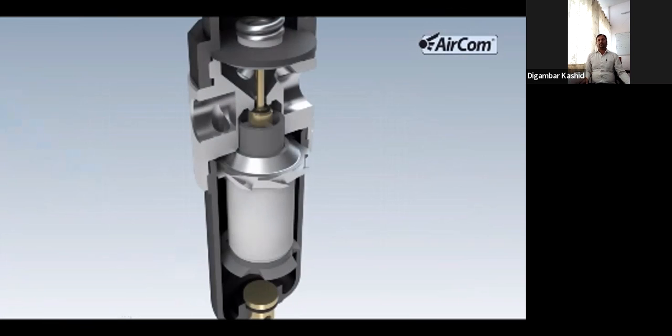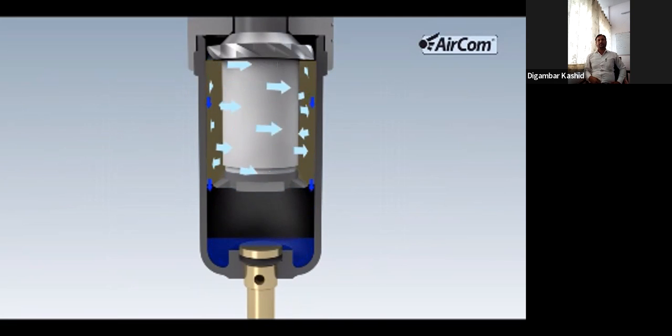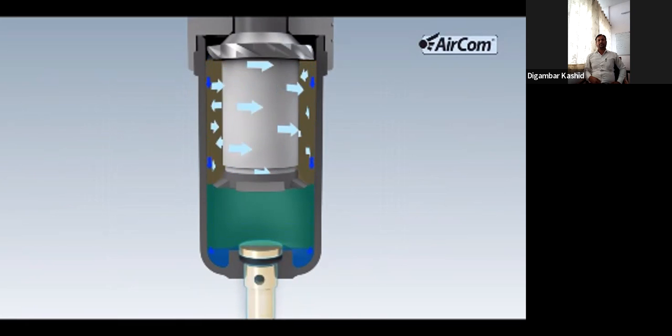The air flows into the filter regulator through the inlet hole, marked dark blue here, and is brought into rotation by the canted wings of the twist cap. This rotation, also referred to as cyclone effect, flings water particles in the air against the filter wall, which then flow down to the container's base. The divider prevents the collected water, referred to as condensate, from being picked up by the airflow again. It divides the filter into a flow zone and a slowdown zone. The condensate collects in the slowdown zone and can be removed from the filter regulator through a drain.